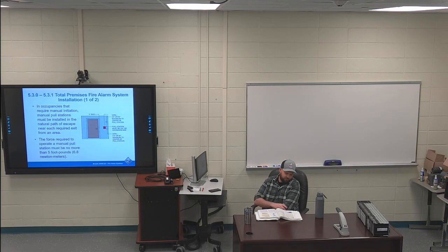First bullet point on page 44 is highlighted. The force required to operate a pull station must be no more than 5 foot-pounds. Can't be crazy hard to pull one of those pull stations. A lot of them have a little glass bulb that they break whenever you pull them.